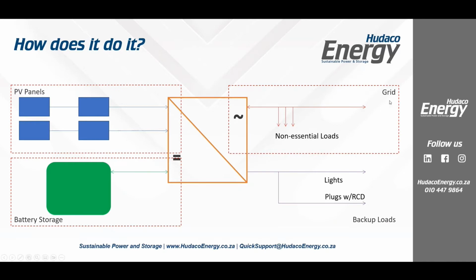So on the AC side, we've got our grid port. And next to that, we've got what we call our backup port, or our EPS, our emergency power supply port. And on this, you'll see I'm actually drawing, even though it's one output on the inverter, I've actually drawn it here with two separate outputs, just because that seems to be the most common way DBs are built in South Africa, where we put all of our plugs on earth leakage and a lot of the lights are not on earth leakage, so that if there is a trip or there's an issue here somewhere, at least you can still see what's happening in the daytime. Please remember, if you did choose to put a geyser or whatever else on your backup port, you would need to have that here on the one with the residual current detection, or the earth leakage as we call it.